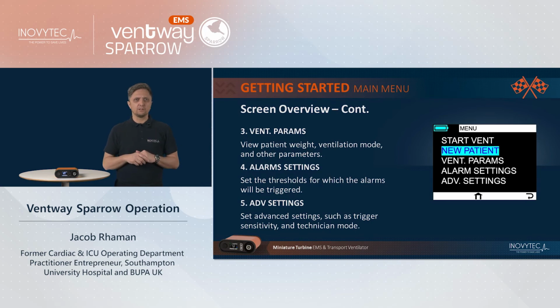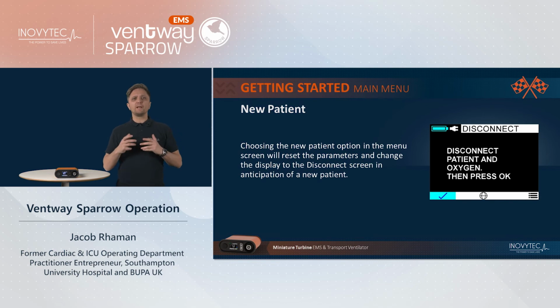Vent parameters. Here you may view the patient weight, the ventilation mode and the parameters. Alarm settings. Set the threshold for which the alarms will be triggered with this option. And advanced settings. Set advanced settings such as trigger sensitivity and technician mode. Let's go into a bit more detail and start with new patient. Choosing the new patient option in the menu screen will reset the parameters and change the display to the disconnect screen, ready for a new patient.